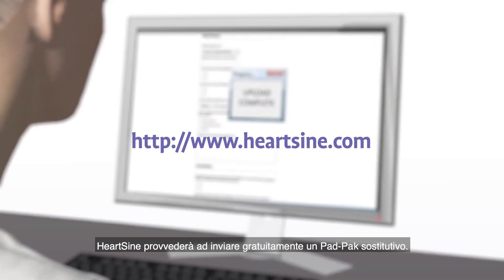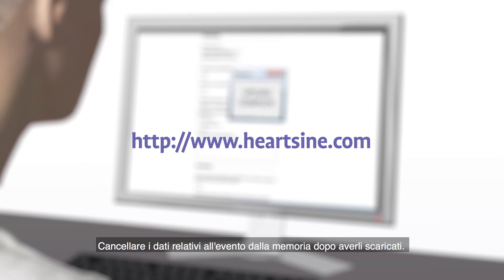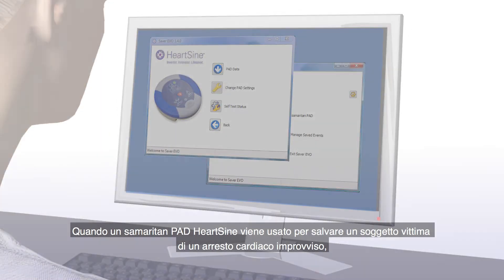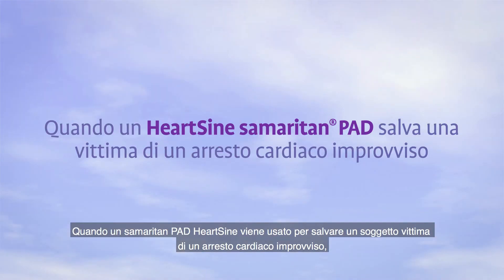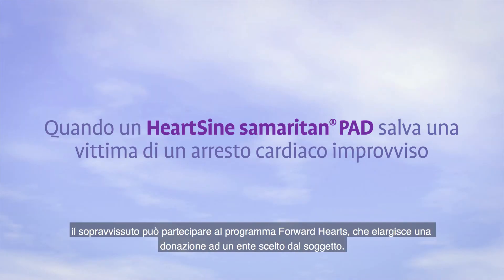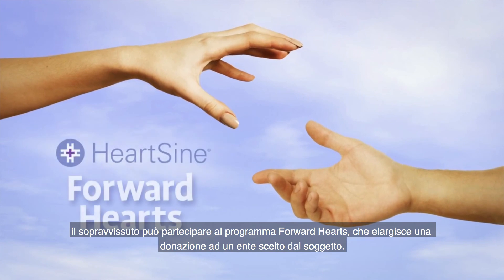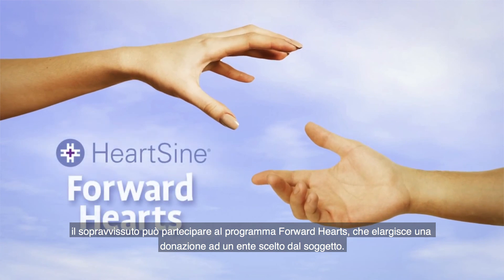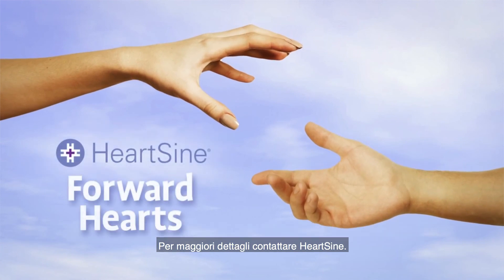HeartSine will send you a free replacement Pad-Pak. After downloading the event data, please erase the data from memory. If you need assistance to do this, contact HeartSine Technical Service. When a HeartSine Samaritan PAD is used to save a victim of sudden cardiac arrest, the survivor is eligible to participate in the Forward Hearts program, which provides a donation to an organization of the survivor's choice. Contact HeartSine for details.